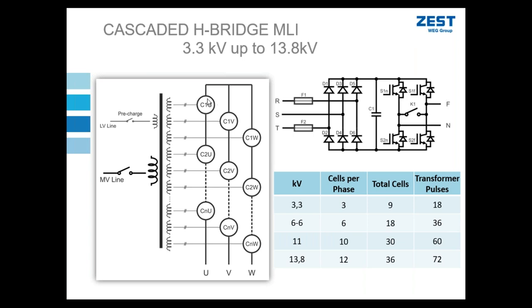These low voltage IGBTs, we normally use 690 volt power cells. Each power cell looks like a single phase low voltage VSD as shown, and we can string them together in series to achieve anything from 3.3 kV using three cells per phase as shown. That means 9 total cells, 3 in each phase, 3, 6, 9.